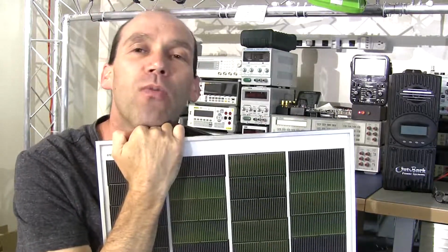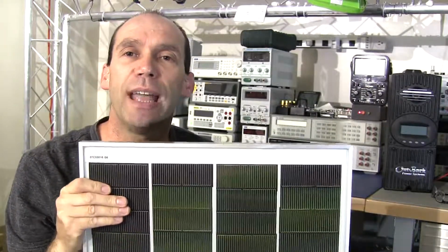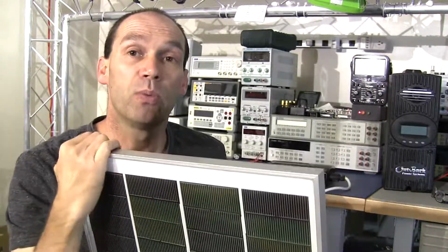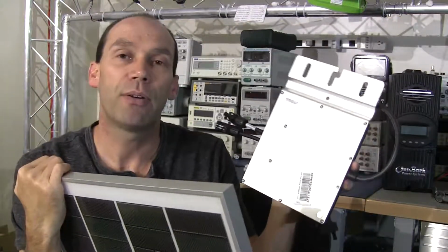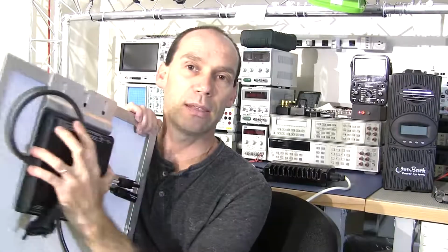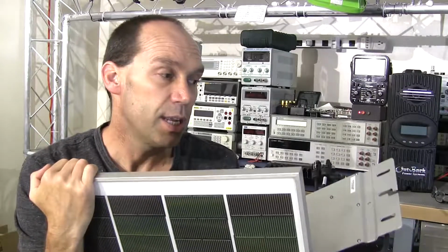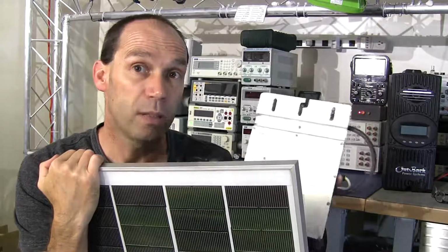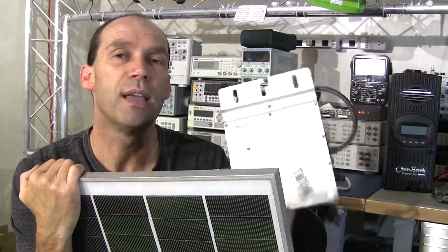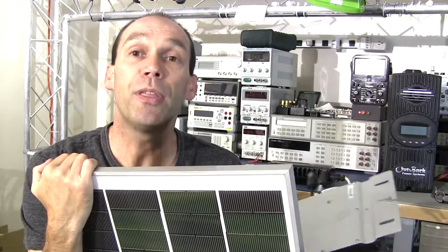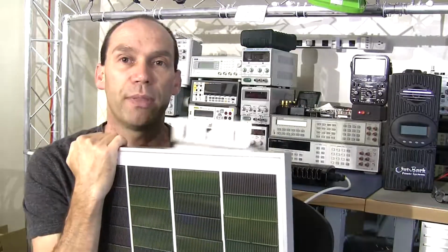Right then, before we end off, what about the future? Now, the one thing I have mentioned before, which will be coming in the future, is actually AC panels. So at the moment, when I go to install the system that I've just purchased, I have to take these Enphase microinverters and mount them on the back of the solar panels, and then mount them on the mounting system. There are things you have to take into account, like the earthing of the solar panels and these microinverters. The one benefit of these 4th generation Enphase microinverters is that they've got an integrated grounding system. So in theory, you don't have to have a separate copper wire grounding the system together. But I still have to mount these on the back of panels.